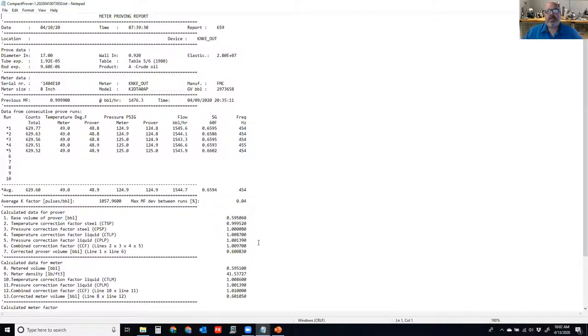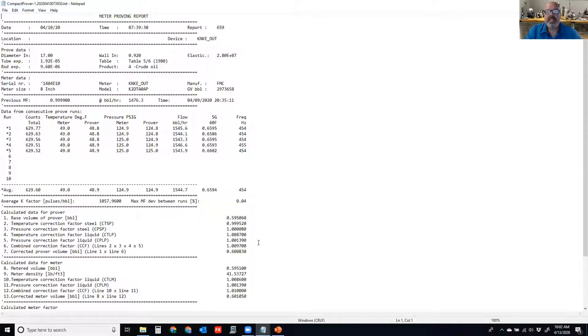What we need on a proving report is the ability to generate the same number — to do the math and generate the same result that the flow computer or software created. There may be side calculations for the effects of temperature and pressure on the steel or liquid whose math isn't presented, but the result — the CTL calculation — is on here because it affects the volume calculated for both the meter and the prover.